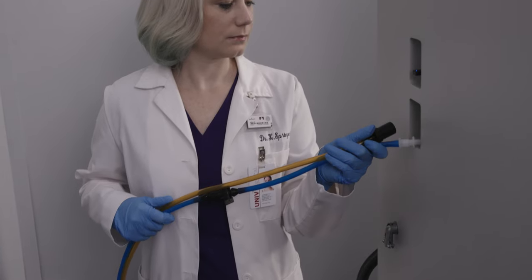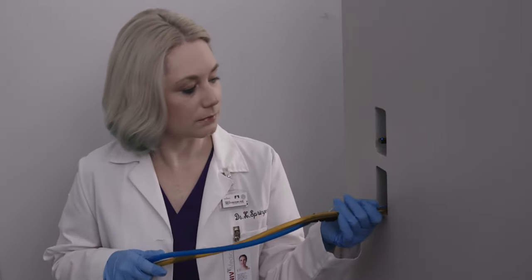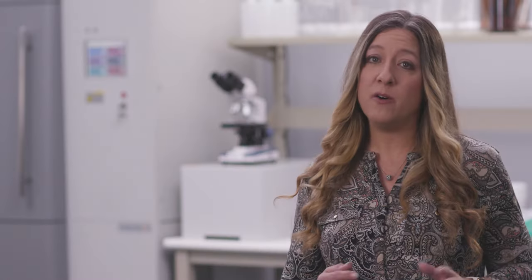For monitoring processes or delivering anesthesia, a side access port provides a safe method to introduce cabling or tubing into the internal chamber, without risk of external radiation exposure.